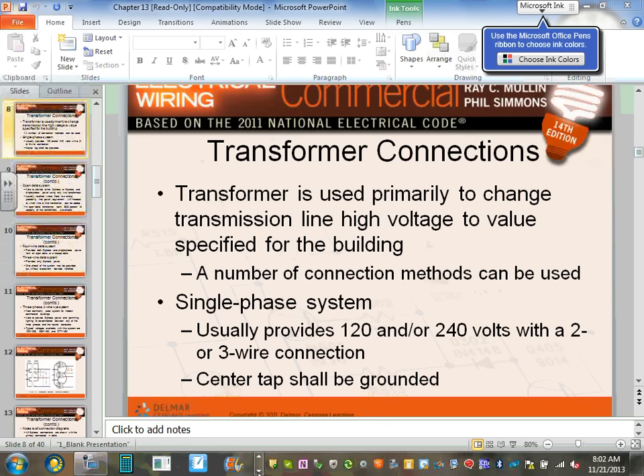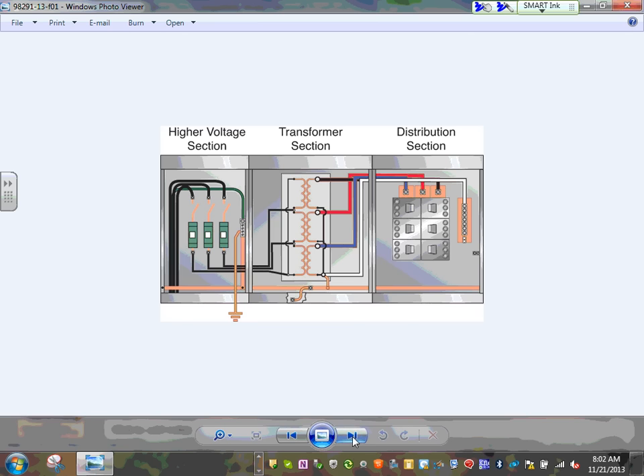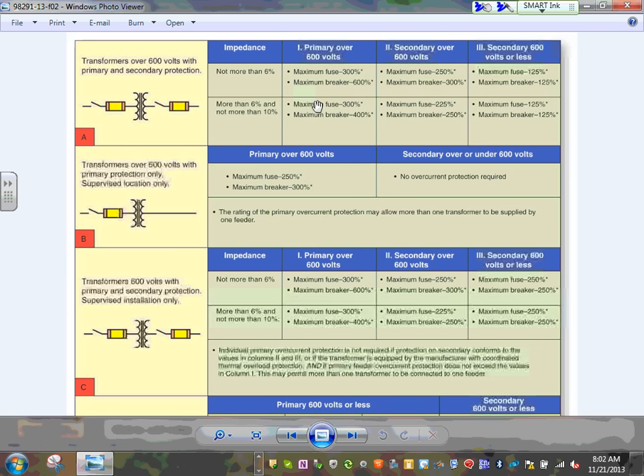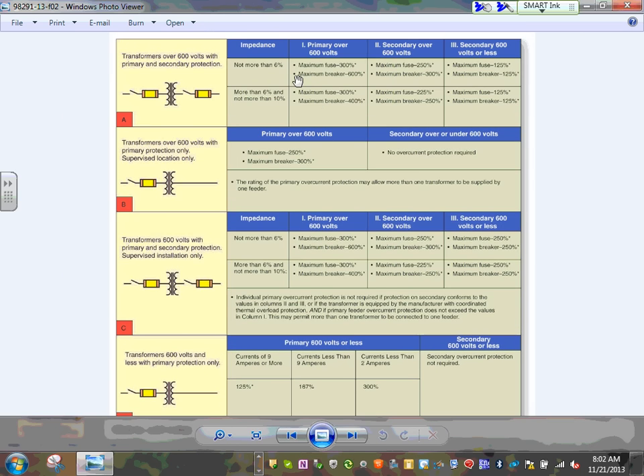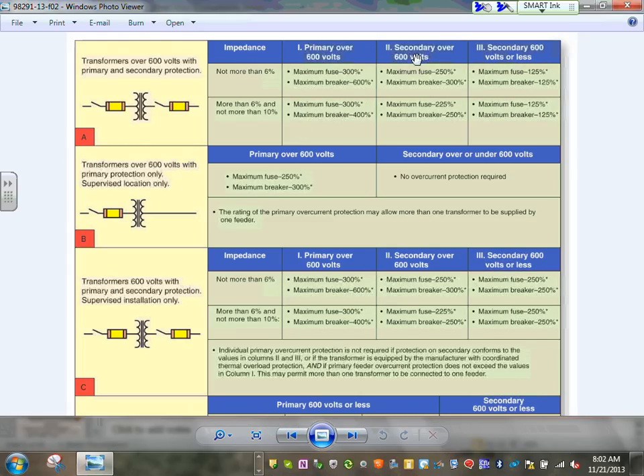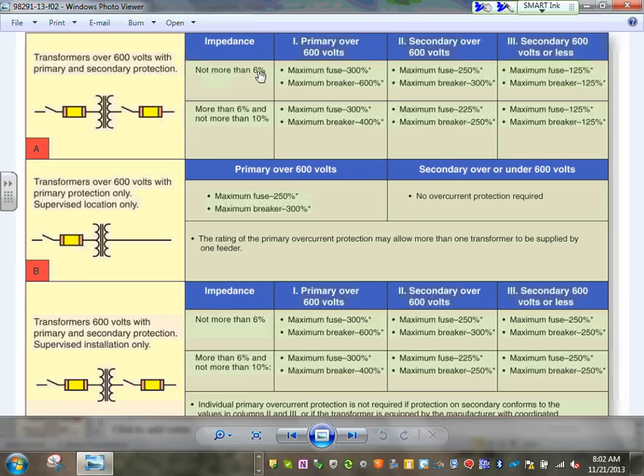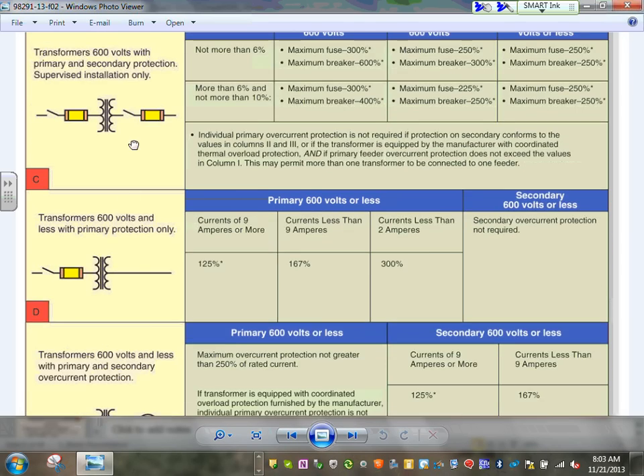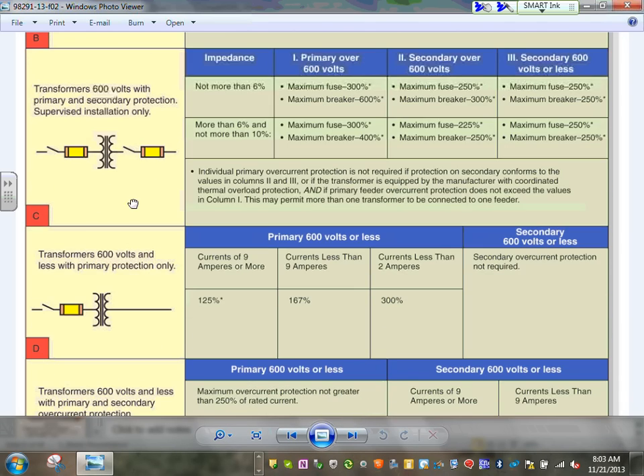And let me just show you as we talk about these guys. I'll show you a couple of pictures that go with it here. So we talked about the substation here. Here's the transformer, the table that talks about the transformer. You can see here's the primary overcurrent protection device, secondary overcurrent protection device, and 600 volt or less, over 600 volt. You can see this is primary and secondary protection. It talks about the impedance, not more than 6. I will give you guys an example of calculating this when we go to the spring, how to calculate overcurrent protection device for transformers. But you can see here the author is dividing it into 5 sections, depending on the primary or the secondary.